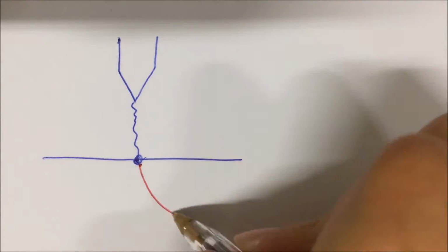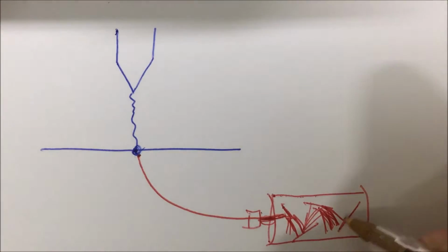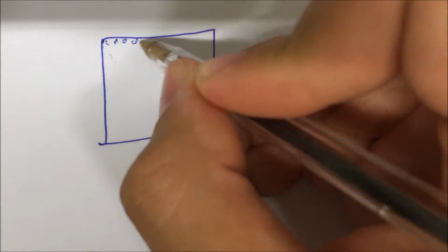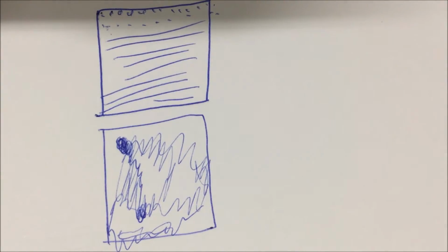But what happens to the photons? The photons are transported with a fiber optics cable and sent to a photomultiplier that gives us a count of how many photons were emitted. We then scan a small area of the sample with a resolution we set, and generate a picture based on the luminescence at each point of the area, with darker areas emitting less light.